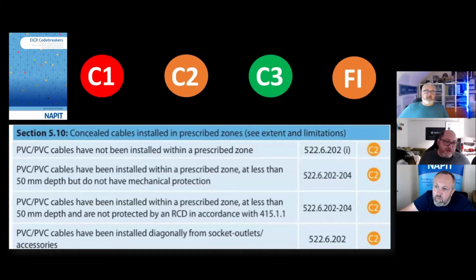The company rewired the kitchen in 1999, and three years later her husband put up the utensil holder. It was out of the zones, but the requirement of regulation 522.6.202 says additional protection shall also be provided - so RCD protection is also needed as well as the zones.